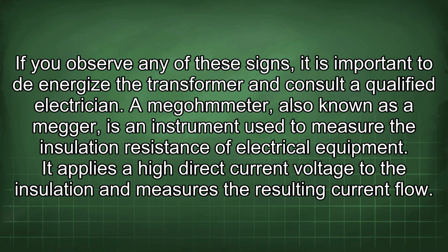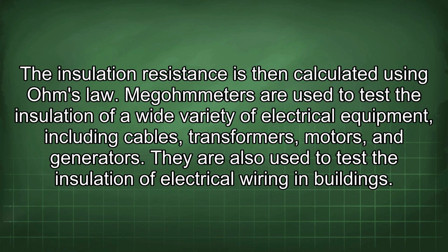A megohmmeter, also known as a megger, is an instrument used to measure the insulation resistance of electrical equipment. It applies a high direct current voltage to the insulation and measures the resulting current flow. The insulation resistance is then calculated using Ohm's law. Megohmmeters are used to test the insulation of a wide variety of electrical equipment, including cables, transformers, motors, and generators. They are also used to test the insulation of electrical wiring in buildings.